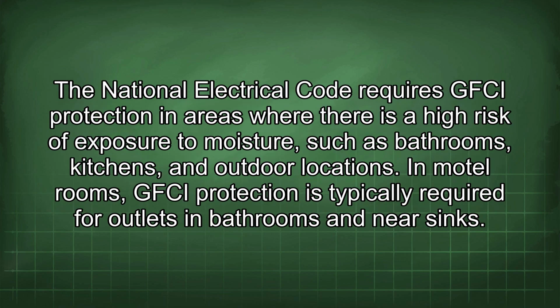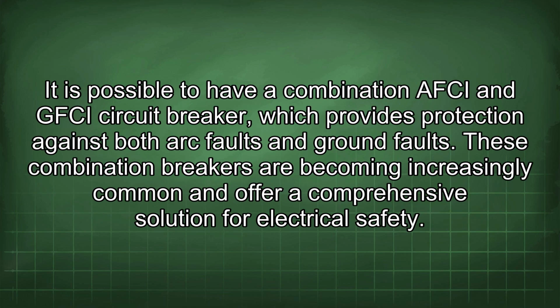The National Electrical Code requires GFCI protection in areas where there is a high risk of exposure to moisture, such as bathrooms, kitchens, and outdoor locations. In motel rooms, GFCI protection is typically required for outlets in bathrooms and near sinks. It is possible to have a combination AFCI and GFCI circuit breaker, which provides protection against both arc faults and ground faults. These combination breakers are becoming increasingly common and offer a comprehensive solution for electrical safety.